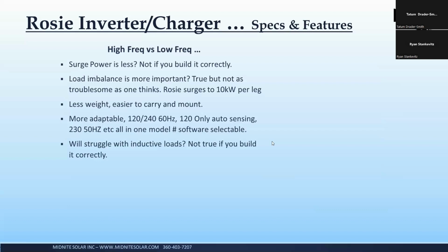So while it is important to balance your loads some if you have a lot of 120 volt loads, it's not super critical, because remember, Rosie will surge to 10 kilowatts per leg. So if you've got a ton of 120 volt loads, just spread them out one on each side of your breaker box so that they're balanced. And that's sort of the electrician in me. That was one of the things I was taught. It's one of the things that our code in the States actually tells the electrician he has to do, is try to balance those loads. So that's the one thing that you do have to pay a little attention to, because you don't have that balancing transformer.